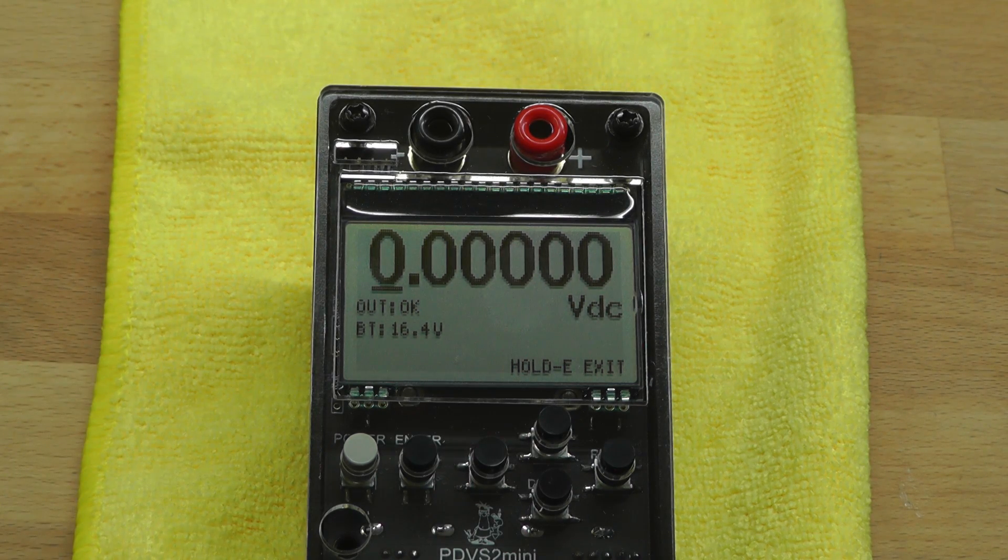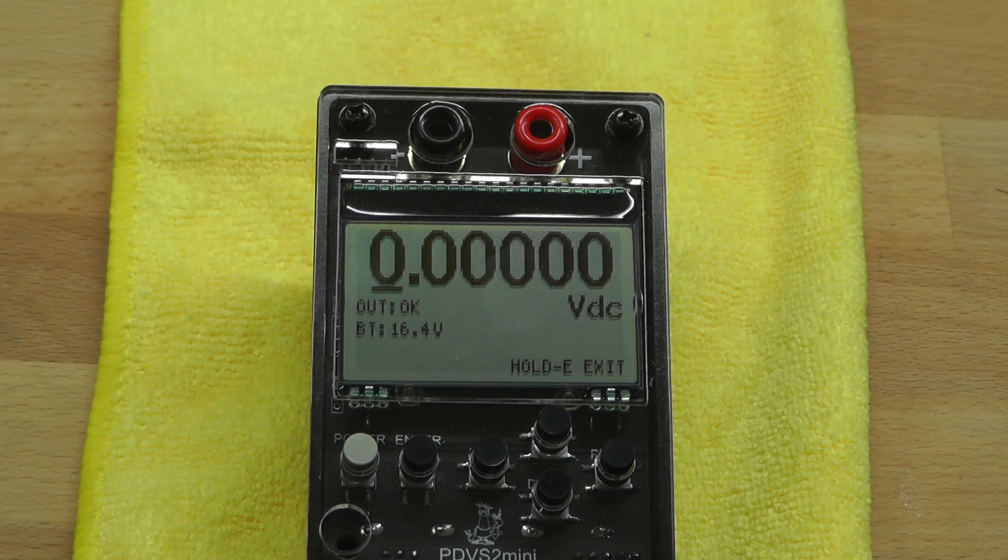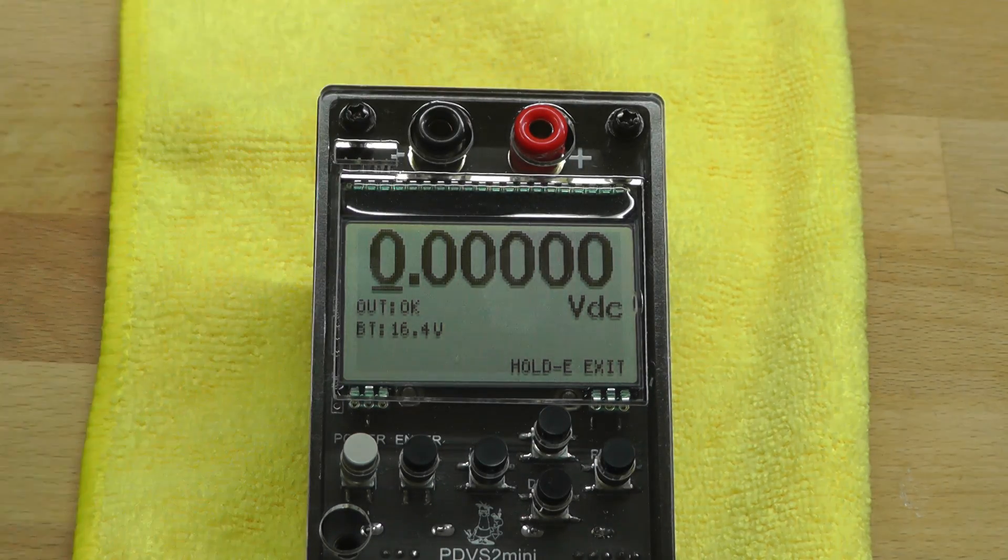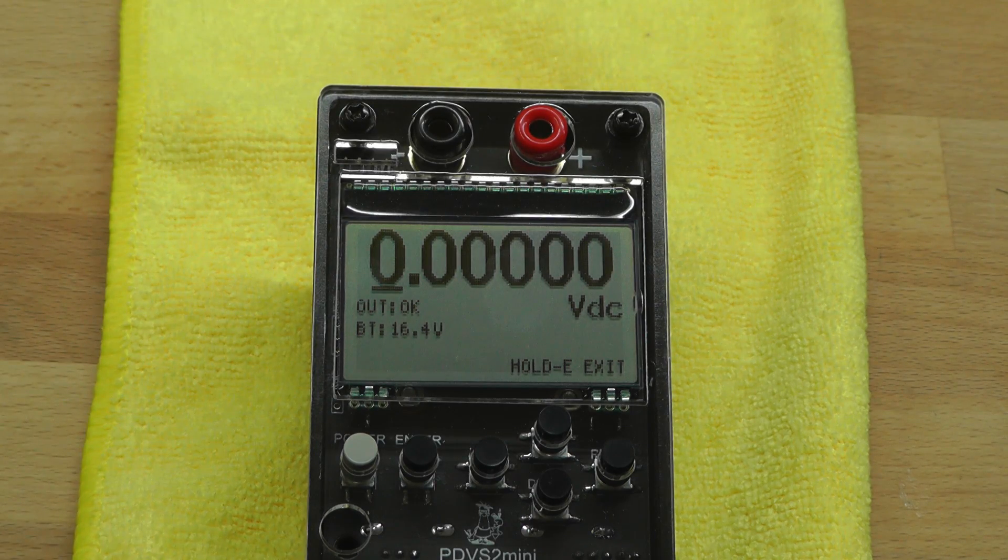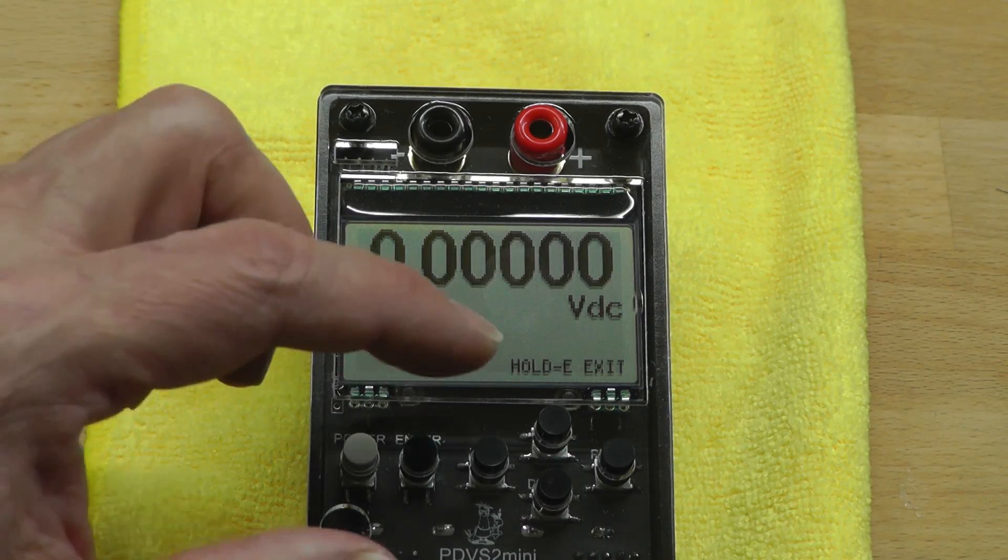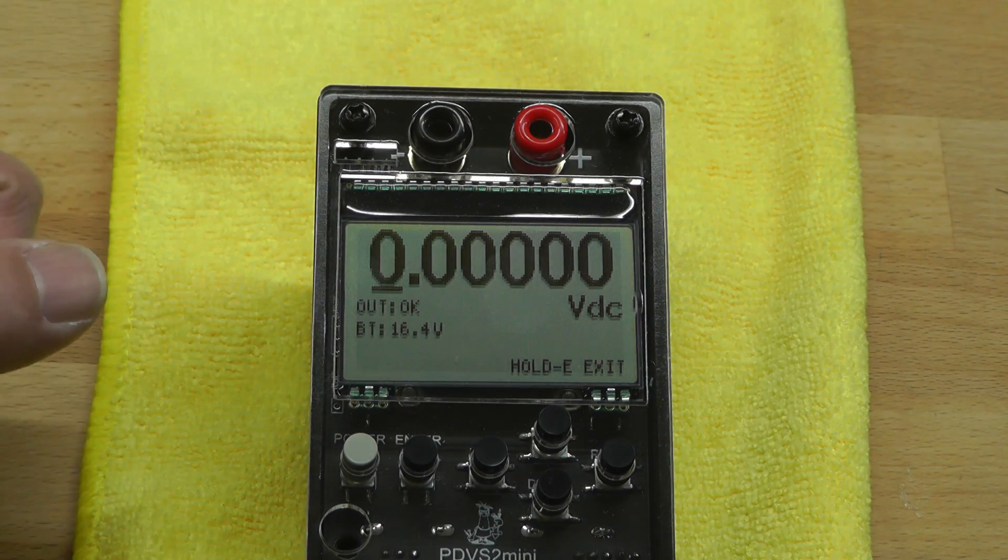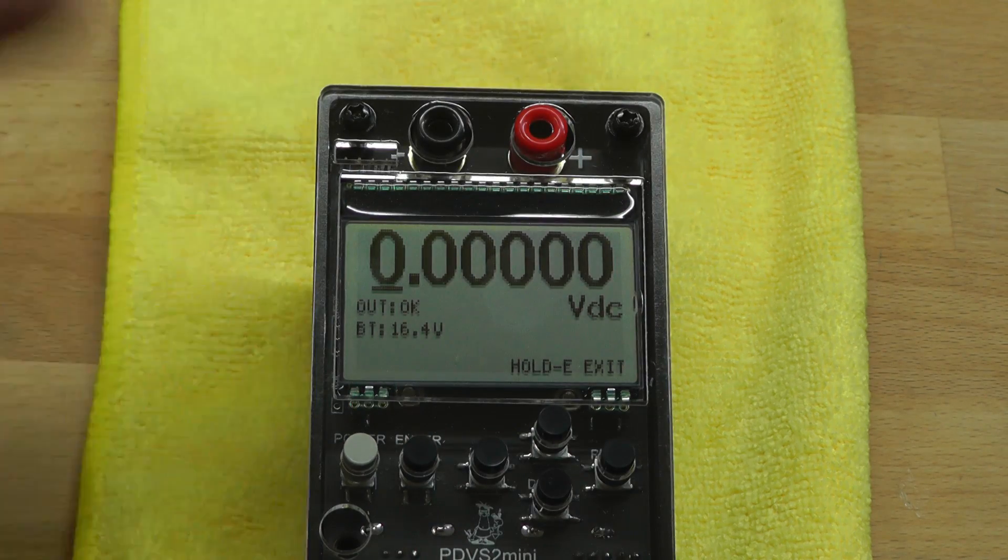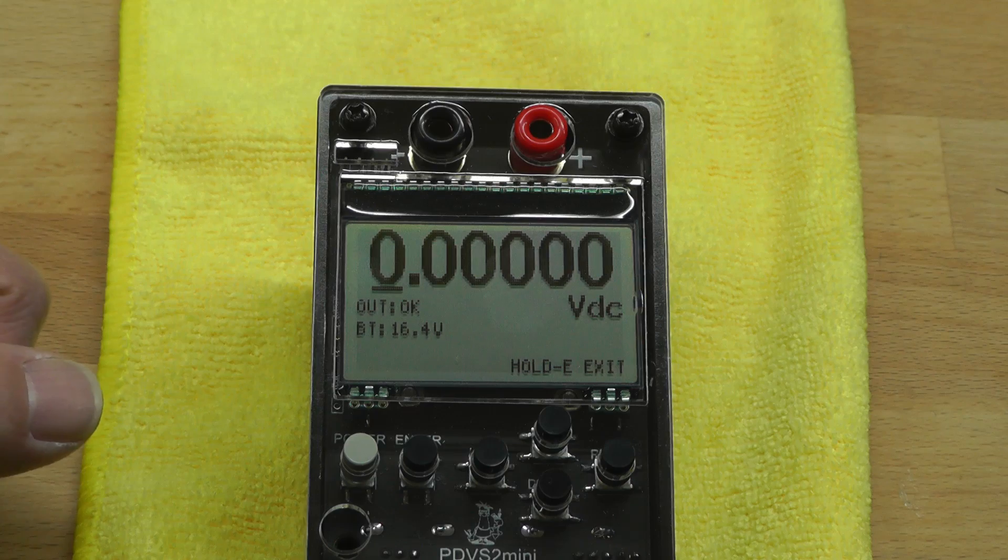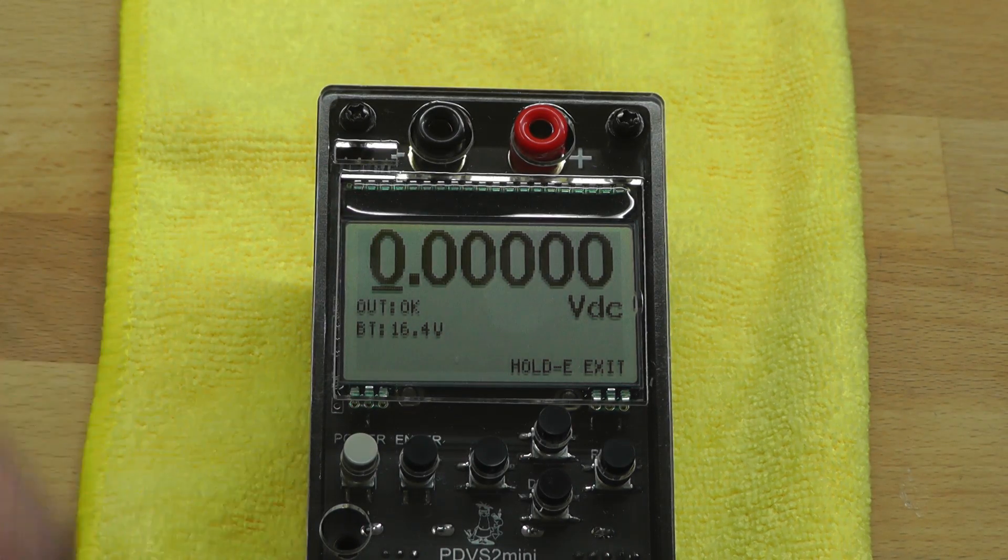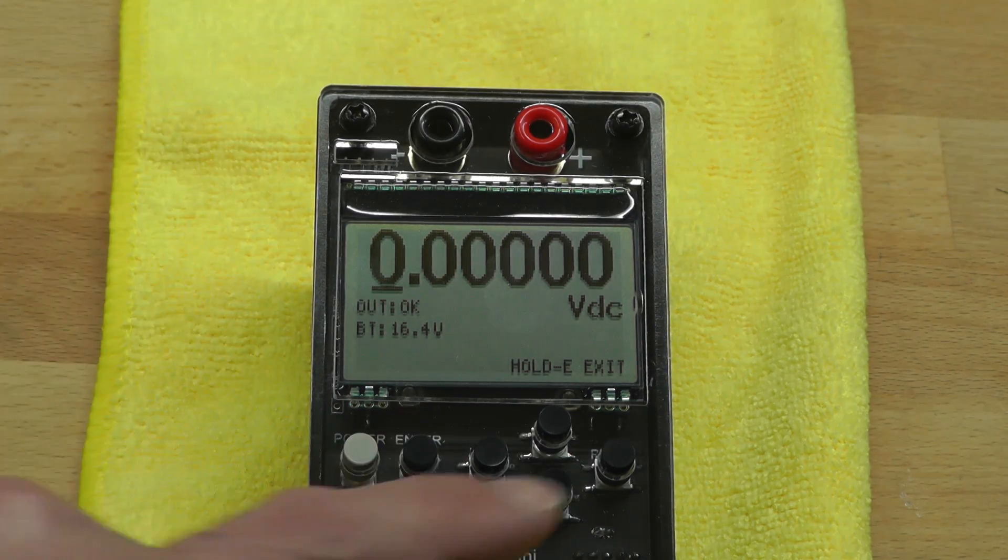i.e. the software will tell the PDV-S2 mini to go to say 5 volts, the multimeter will obviously read that through from the analog output here into the analog input of the multimeter. And then I'll feed what voltage it's reading back to the PC and then the PC can then instruct the calibration set points of the PDV-S2 mini to change until exactly 5.00000 volts is on the display - a full calibration circuit. And once it's achieved that it will move on to the next voltage and so on until all 11 set points are calibrated. And then in fact the software can then instruct the PDV-S2 mini to save that calibration and therefore there's virtually no interaction via the push buttons here to do any of the calibration.